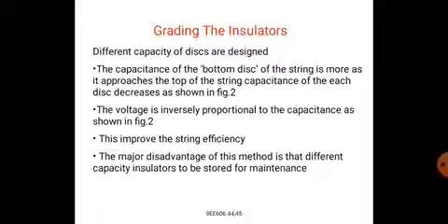And this improves the string efficiency. The major disadvantage of this method is that different capacity insulators have to be stored for maintenance. So in grading of capacity, different capacity discs are designed, so each insulator should be different. The capacitance of the bottom disc of the string is more, and it decreases as it approaches the top of the string.